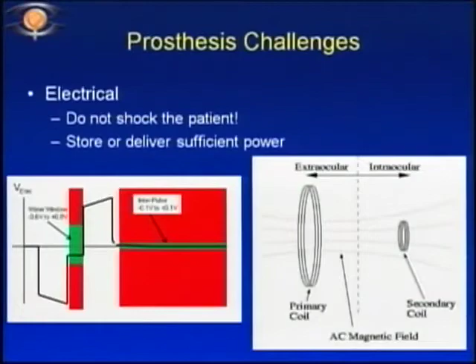On the right, we see how we are going to actually deliver this power to a device. We saw in one of the LVAD pictures there was a coil. We're actually wirelessly transmitting power from the outside of the body to the inside of the body. If you take a loop of wire and send an alternating sinusoidal current through it, you create a magnetic field in space that just passes through the body. If there's another loop of wire inside the body that's exposed to that magnetic field, you will induce an alternating sinusoidal voltage on that coil.